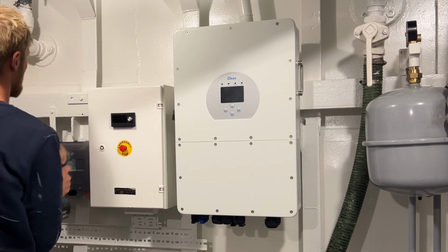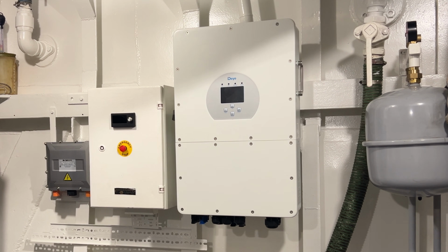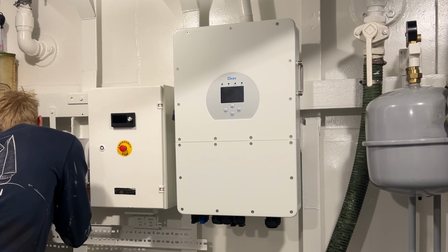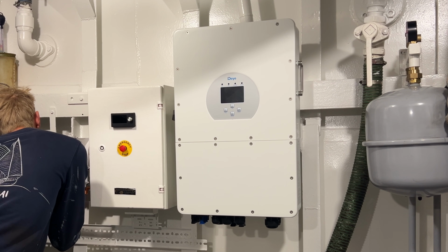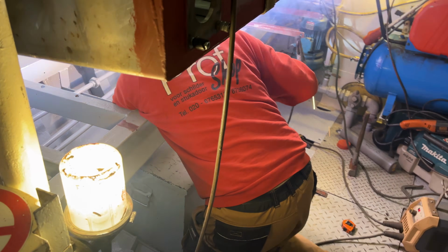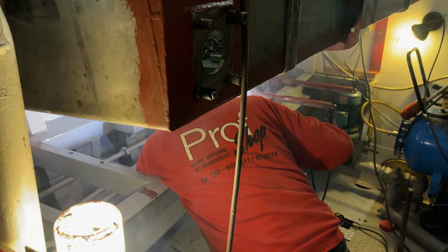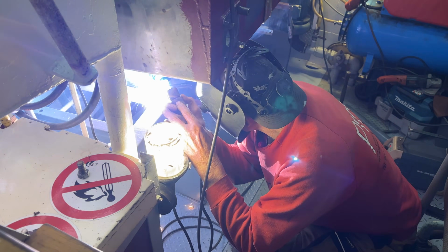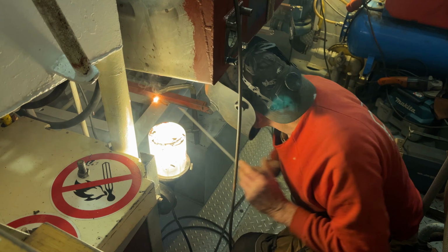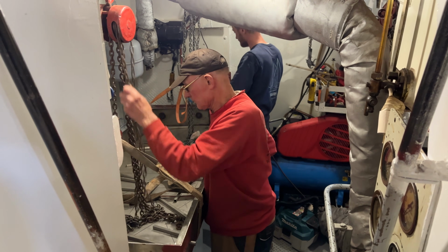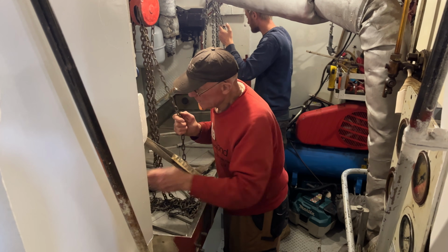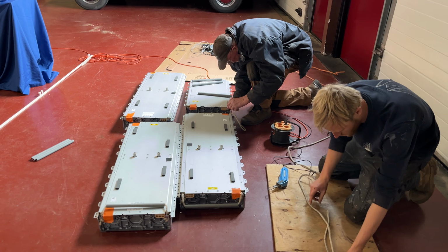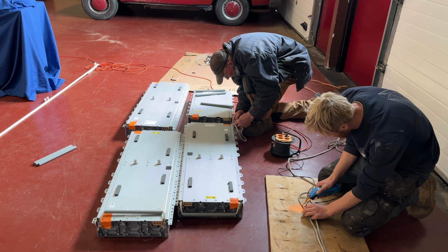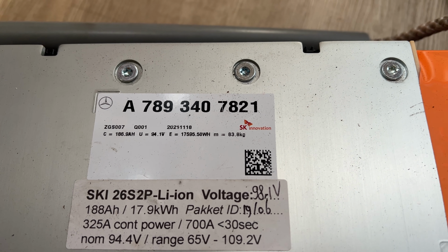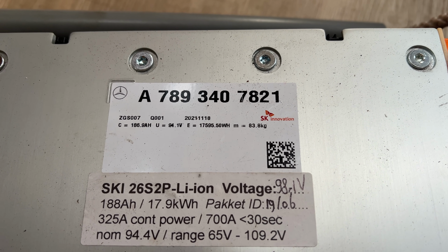This charger also inverts up to 20 kilowatts of battery power to 3-phase AC power, which means our 15 kilowatt bow thruster can run directly from it. And we don't need to start a separate generator anymore during maneuvering. Now we can install the battery box and the batteries themselves. These batteries are made by the Korean company SK Innovation for the Mercedes-Benz supply chain. So they are top-tier automotive batteries. But they never went into a vehicle. They are unused modules that EV Europe acquires through their normal supply channels.